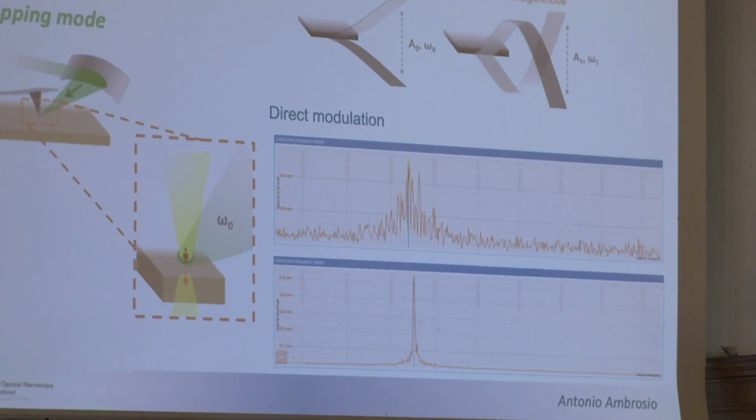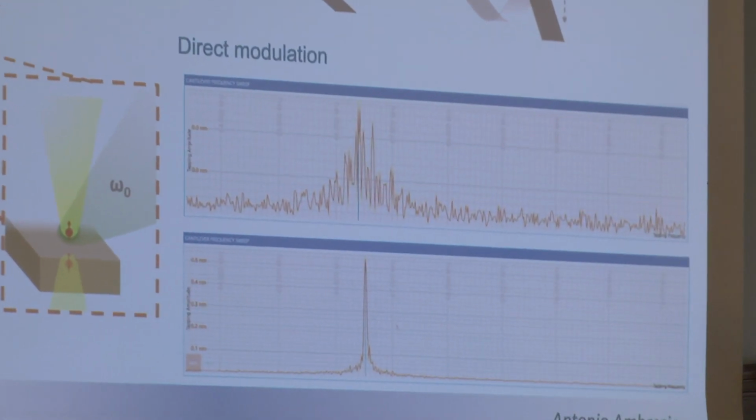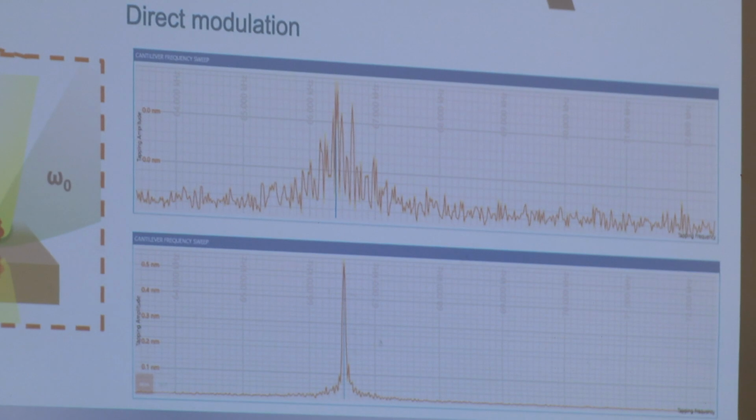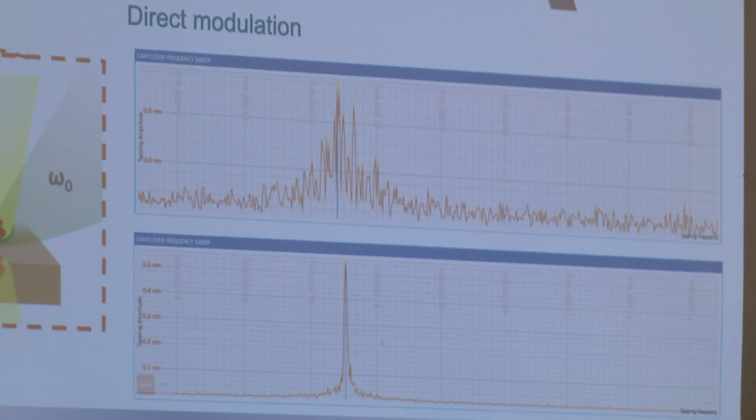And actually, I want to show you something that you can do yourself with your neaspec SNOM. If you do thermal tune, you put the driving piezo at 0 and you sweep the frequency around the oscillation of the cantilever, the first mode, you eventually will see this. It depends how your machine is performing, and what is the stiffness of the cantilever. But anyway, you see something around where the first mode is supposed to be.